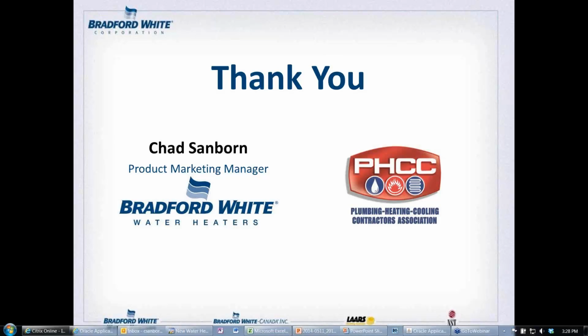Can you explain again on the electric heaters how you can have an EF over 1? Yeah, that's a good question as well. So an EF over 1 means that you're 100% efficient or over 100% efficient. On the electric side, you can achieve this because of the heat pump technology that's on top of the water heater. The heat pump portion of the water heater is not creating energy. It's essentially stealing heat from another source, and in this case, it's stealing heat from the air.